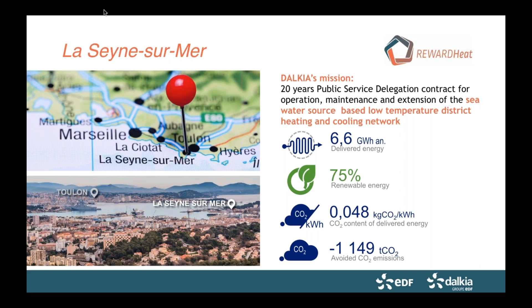So if we go to the next slide, please. You see a little bit the scheme of how this works. Just to say, we didn't design this network—we inherited it through this open call for tender two years ago. The network was built in the early 2000s. So what we have is a first loop, what we call the seawater loop. We pump the water directly from the port at 4 meters depth, up through an exchanger and pumping station, and the seawater is pumped back into the sea at the same depth.